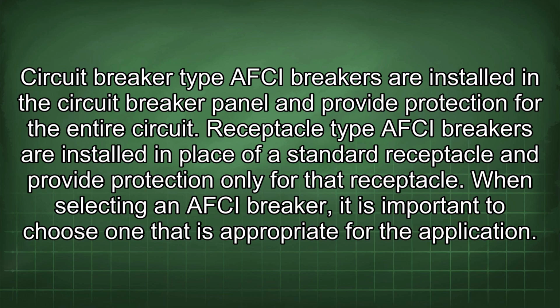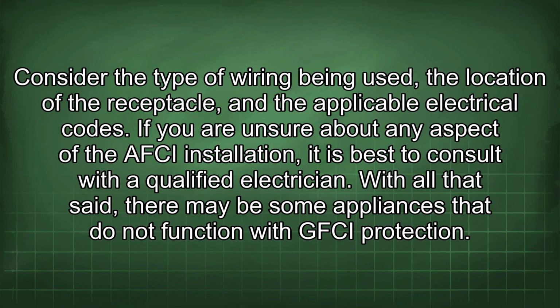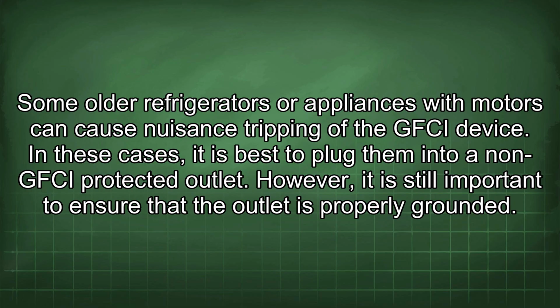When selecting a GFCI breaker, it is important to choose one that is appropriate for the application. Consider the type of wiring being used, the location of the receptacle, and the applicable electrical codes. If you are unsure about any aspect of the GFCI installation, it is best to consult with a qualified electrician. With all that said, there may be some appliances that do not function with GFCI protection. Some older refrigerators or appliances with motors can cause nuisance tripping of the GFCI device. In these cases, it is best to plug them into a non-GFCI protected outlet. However, it is still important to ensure that the outlet is properly grounded.